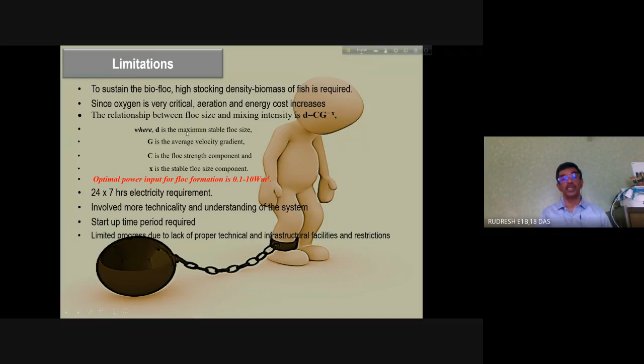And what is the energy cost? The relationship between floc size and mixing intensity is D = CG^-x. So what does it indicate? D is the maximum stable floc size, G is the average velocity gradient, C is the floc strength component, and x is the stable floc size component. If you go for calculating in detail, I have compacted it here, that is why the details are not here. The optimal power input for floc formation is 0.1 to 10 watt per meter cube. Ultimately, we have to calculate in terms of your energy requirement, in terms of your electricity requirement. So this is the optimum power requirement, 0.1 to 10 watt per meter cube.